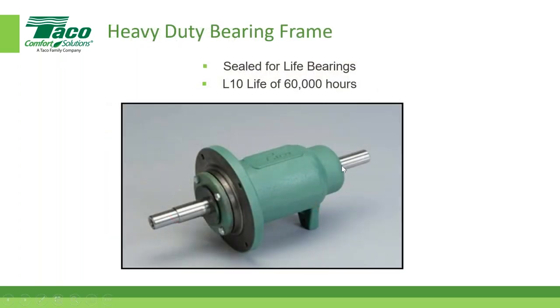Heavy duty bearing frame. So I talked about the bearing frames. There's that stainless steel shaft. And we have standardized on sealed for life bearings. All right, and the L10 life, some of you may see that in the spec. I know we see it, some of our reps see it on a somewhat regular basis. These bearings are good for at least 60,000 hours. They're L10 life, if not longer. So they do not require lubrication.